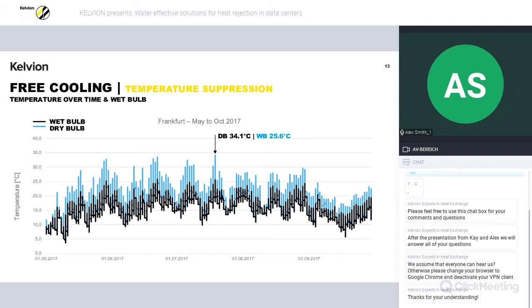cooler. However, semi-wet solutions such as adiabatic coolers and augmented units are able to reduce the air temperature somewhere between the dry bulb and the wet bulb temperatures. This is known as the effective air-on temperature and is the temperature which the heat exchanger coil sees. If we were to use a semi-wet solution consistently throughout the year, we could use the least amount of air possible to meet a desired capacity, using the least amount of fan power required, thereby improving PUE substantially and reducing noise levels.